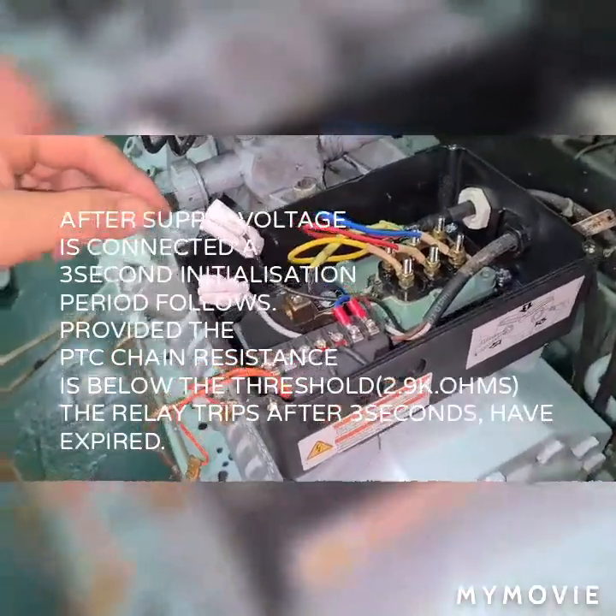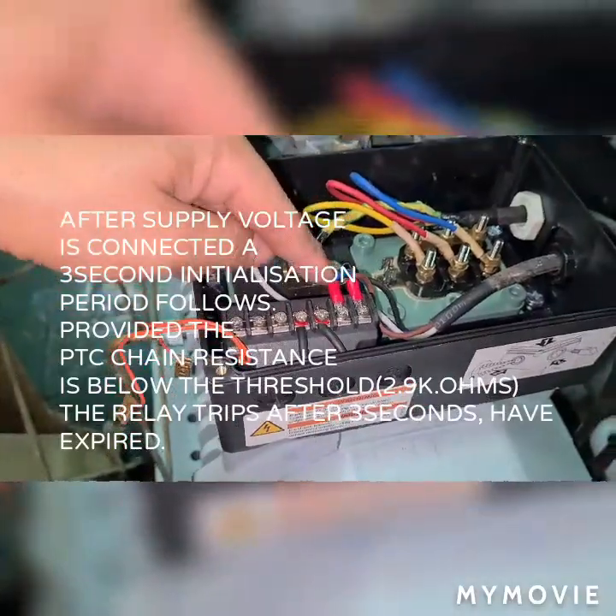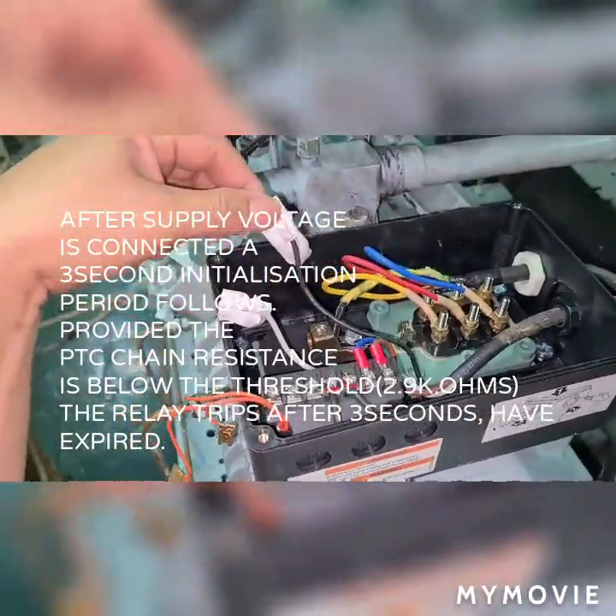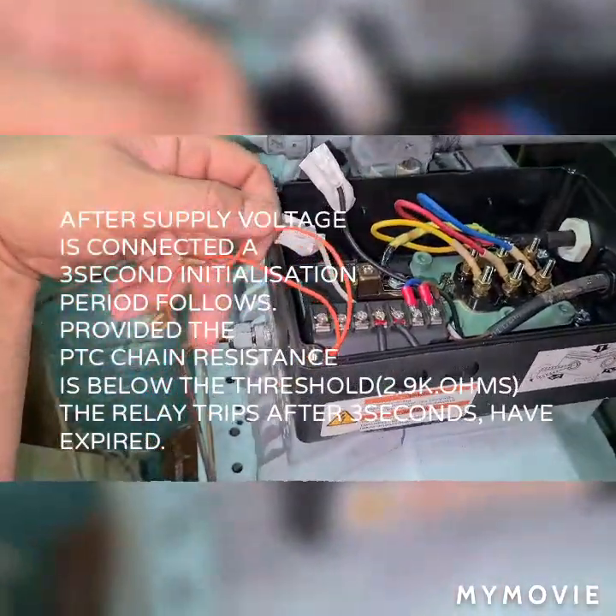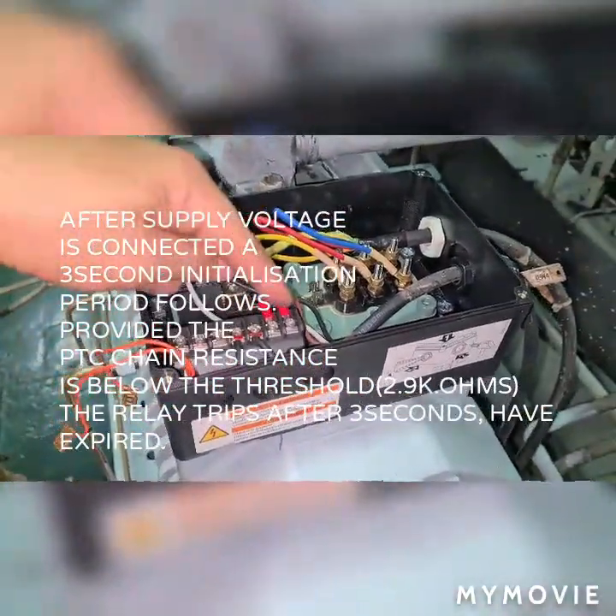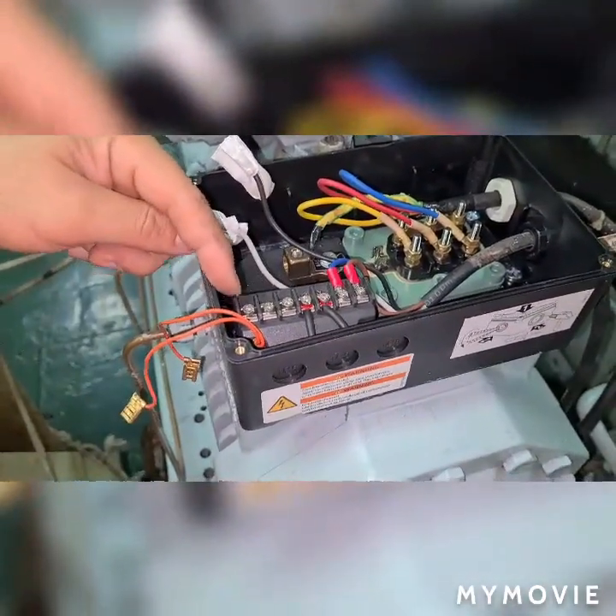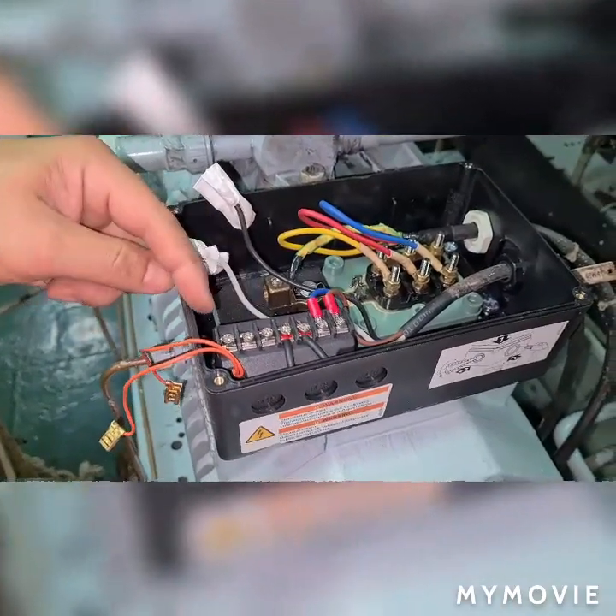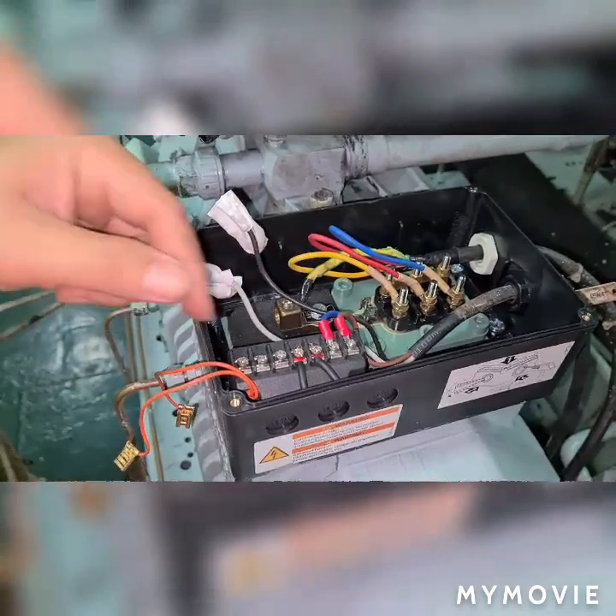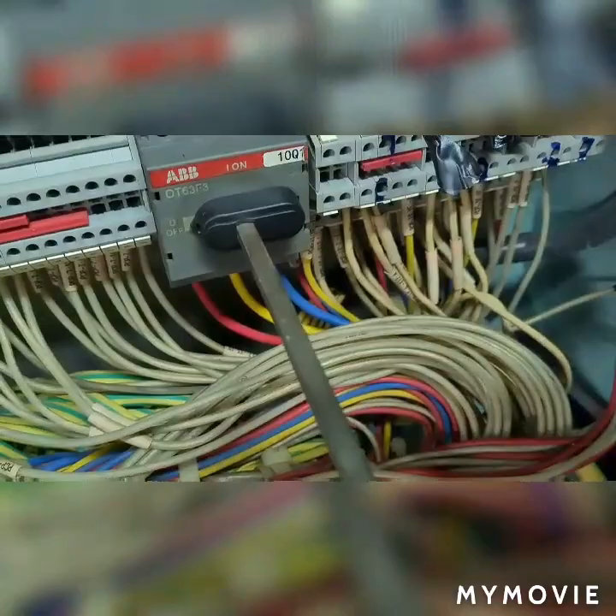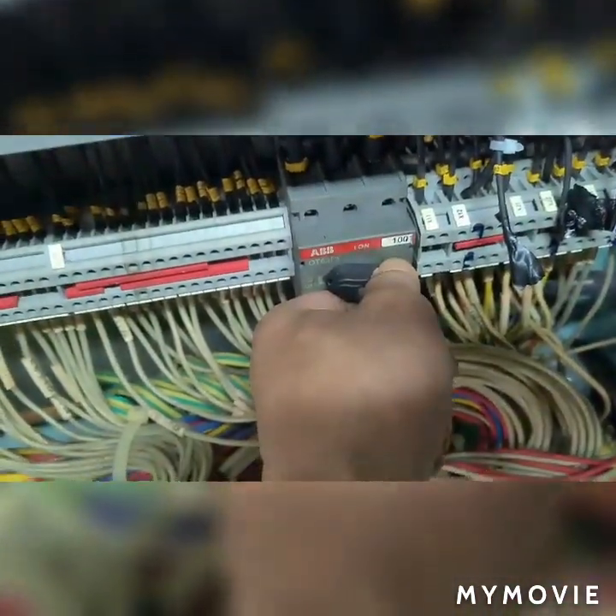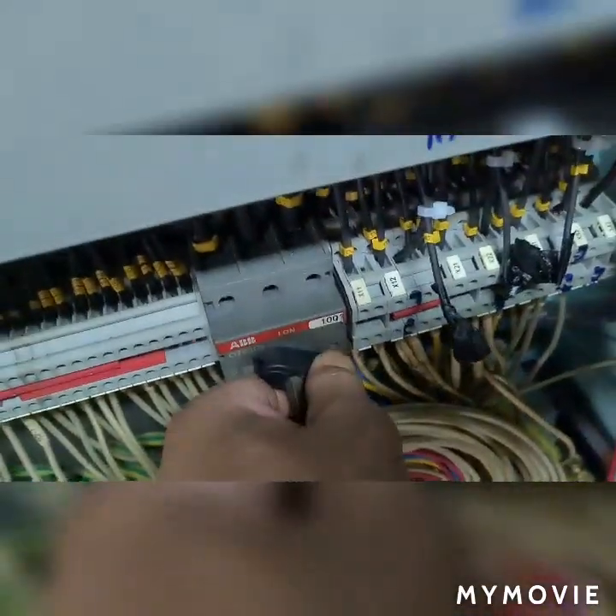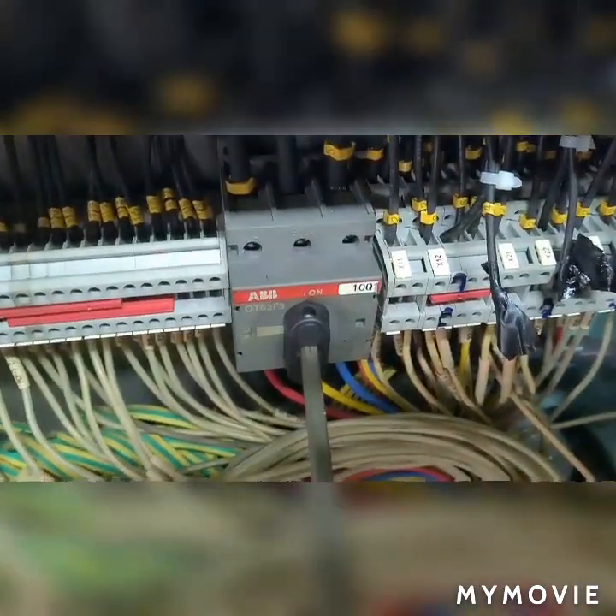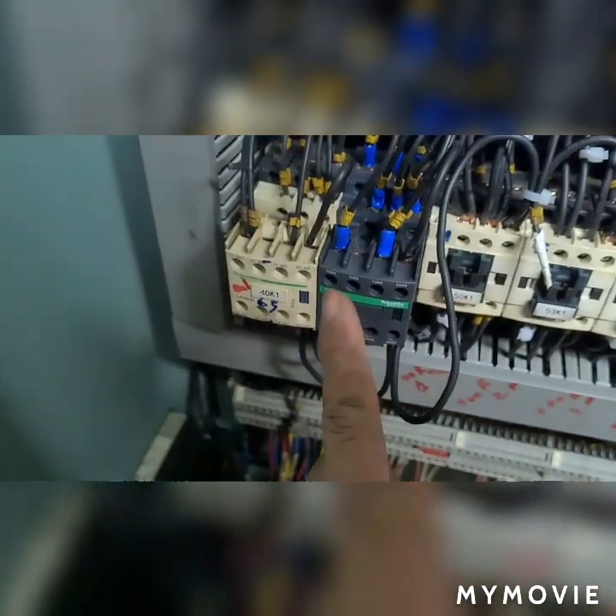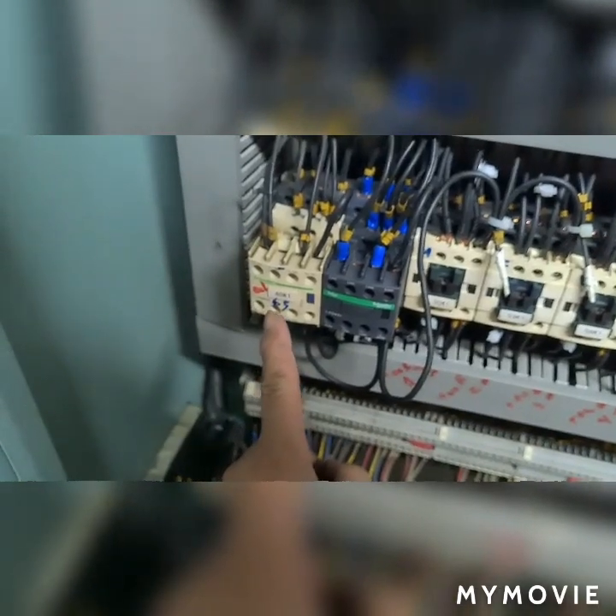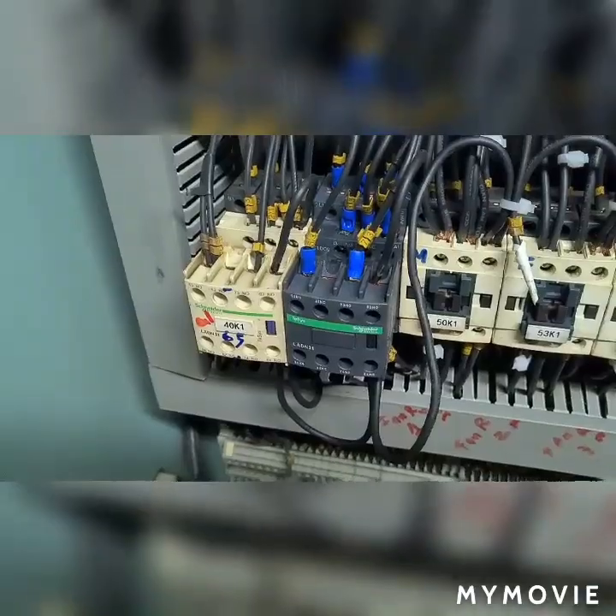As you may see here, I have now the compressor which is made by Bitzer, and I connect and simulate this motor protector relay. I apply 230 volts on terminal L and N, and we further verify if the normally closed contact on this relay remains open. Then we try to start the compressor by pressing the circuit breaker, and as verified, when the motor protector relay is open, the compressor will not be able to start and remains disengaged.